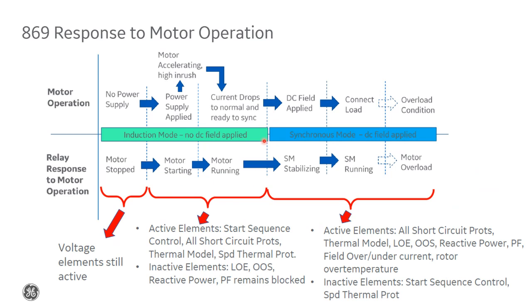So up to this point, we do not have any DC field applied. After this point, when the motor is up to speed, the start sequence control will determine the appropriate time to apply the field, and it'll trigger that application. So that's this point here. As soon as the field is applied, there's a stabilization period. The relay goes into synchronous motor stabilizing mode. Then once stabilized, the load will be connected, and then the relay will go into synchronous motor running mode.